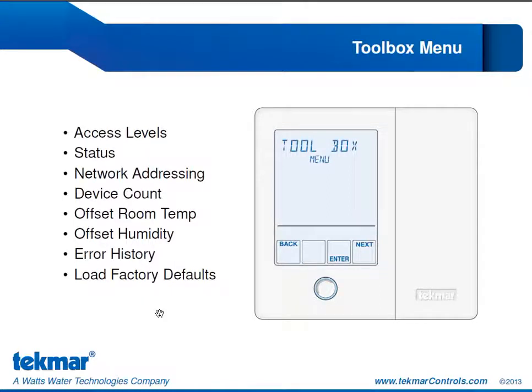Our toolbox menu is very useful for troubleshooting. As a tech person, this is where I start when I'm trying to diagnose a problem on a 557, because it provides so much information to me. Here is where I can configure the access level. So obviously I need an installer to configure the settings of the 557, but once I'm done setting it up, it is advisable to reduce that access level to user, limited, or secure. That way we can try to prevent homeowners from changing settings inadvertently that end up triggering errors on the system.